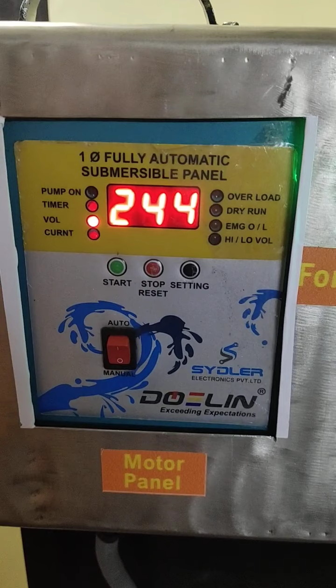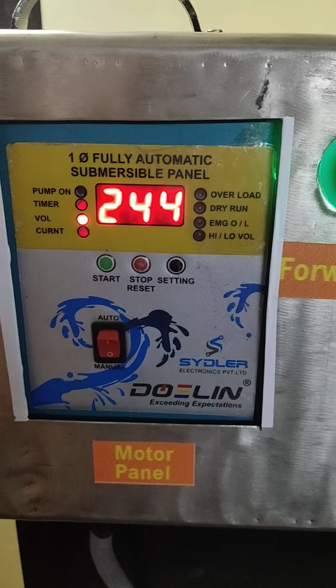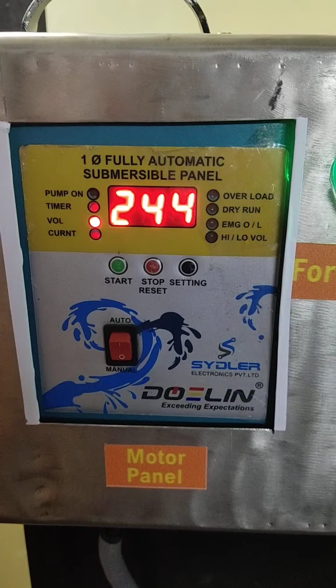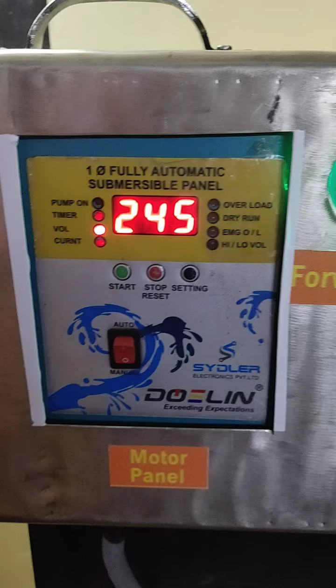And due to the intervals of approximately 5 minutes, the system will work on soaking and flushing - soak it and then wash it. First it will flow the chemical to your heat exchanger, then it will take a soaking effect for 5 minutes, or whatever time we recommend, as per the setting.